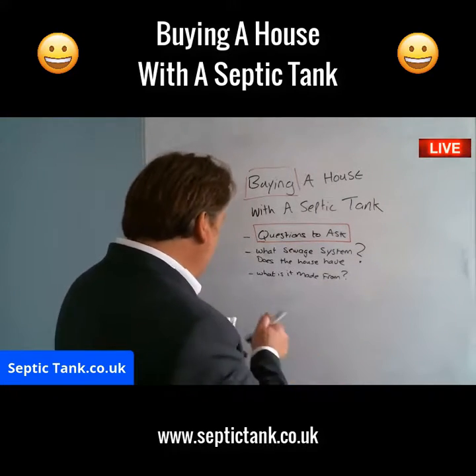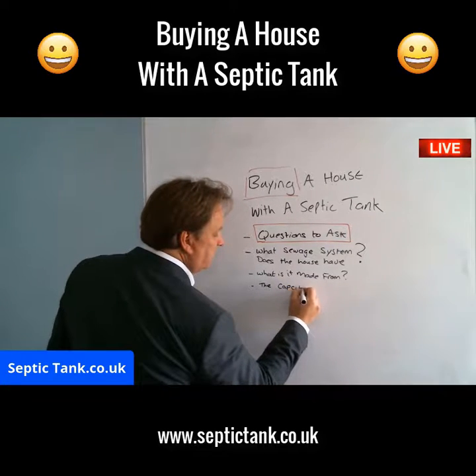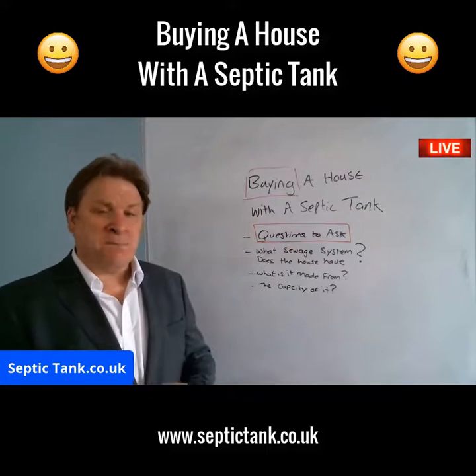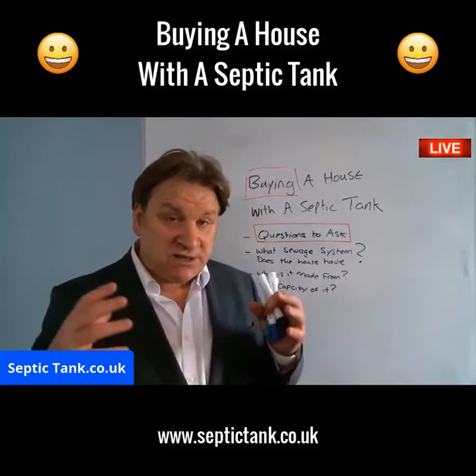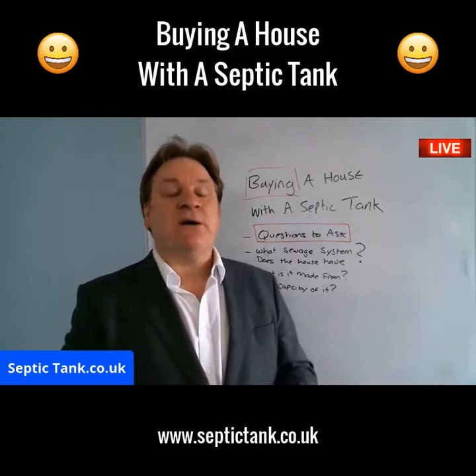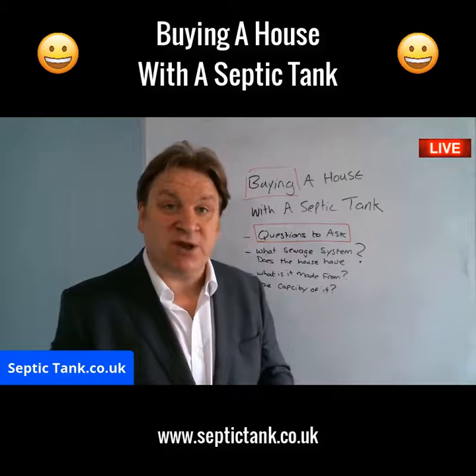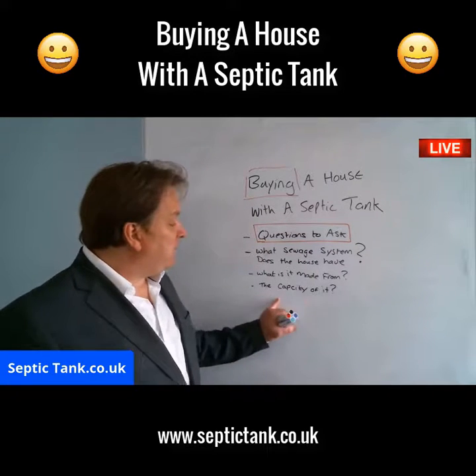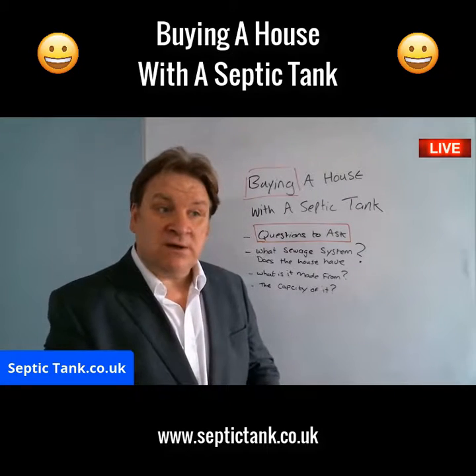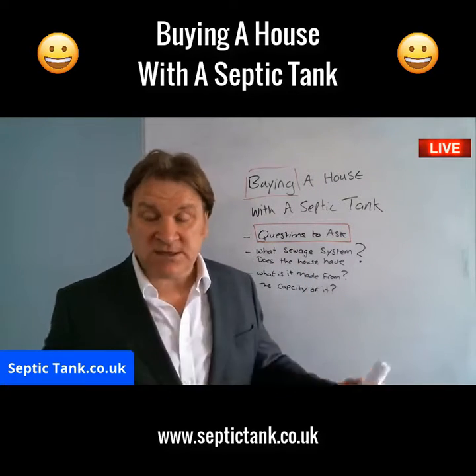All right, so once you've ascertained that, you now need to ascertain the capacity of it. So why is that important? Well, because the government have legislation regarding the size of sewage systems. Just to give you a quick example, the UK government state that on a domestic property, the capacity of the septic tank must be at least 2,800 litres, okay? 2,800 litres. So if you learn that the capacity is 1,000 litres or 1,500 litres, then you know that the septic tank installed into the house in which you're buying is illegal according to the Secretary of State, according to building regs.